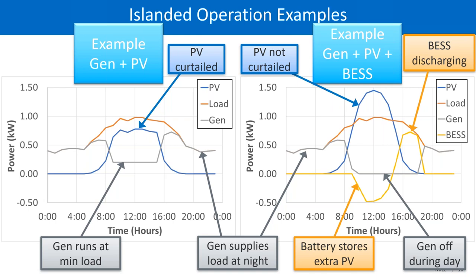The generator can't turn off in this scenario because PV is not capable of making its own voltage, and therefore it has to have a generator there to provide voltage. You don't want the generator to run at no load, so typically it's going to curtail the PV and not allow it to produce too much.